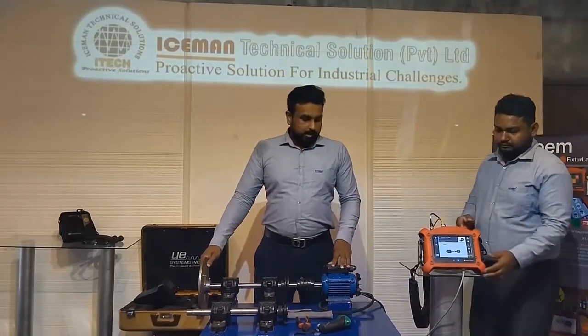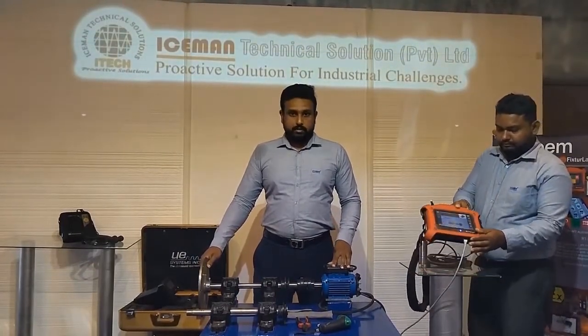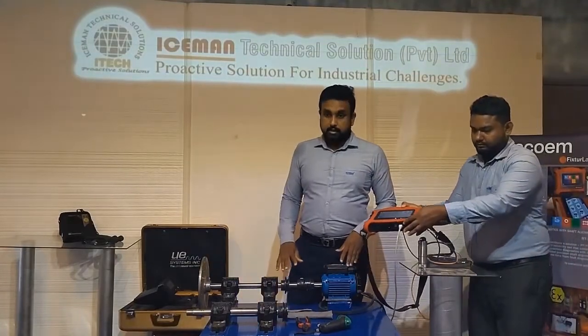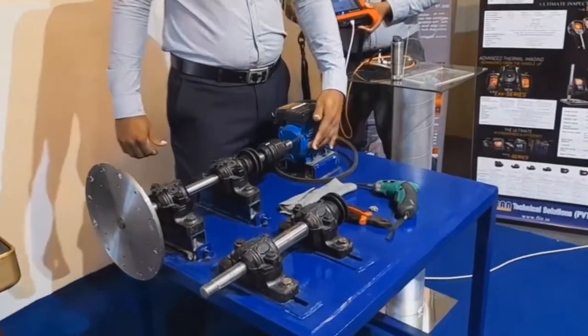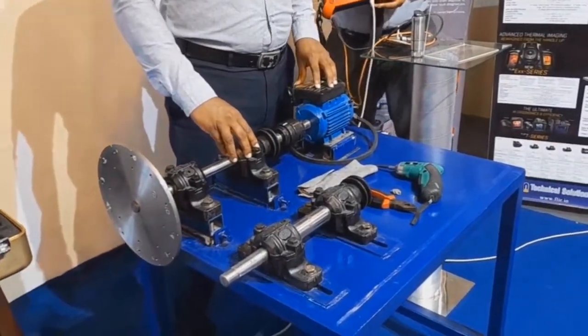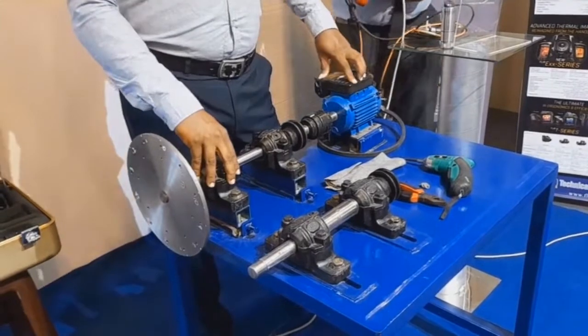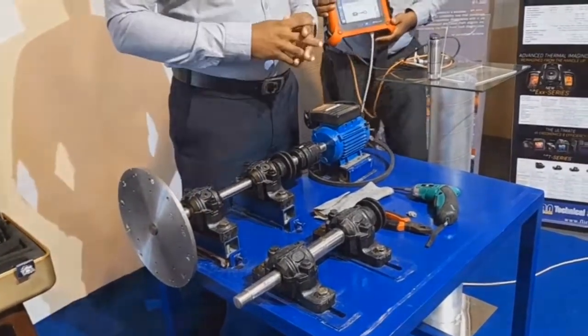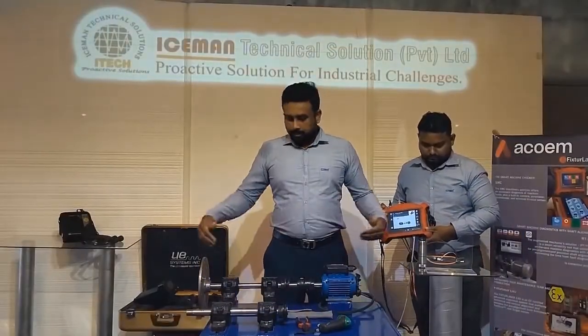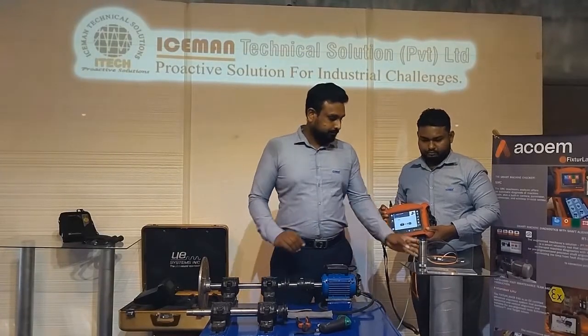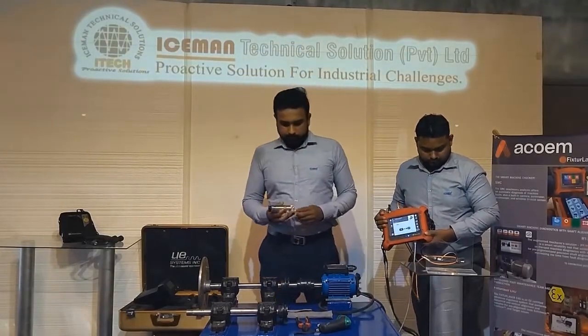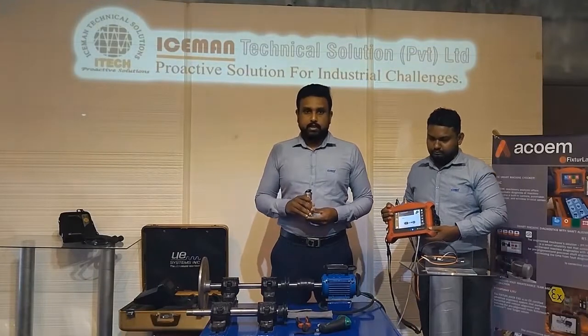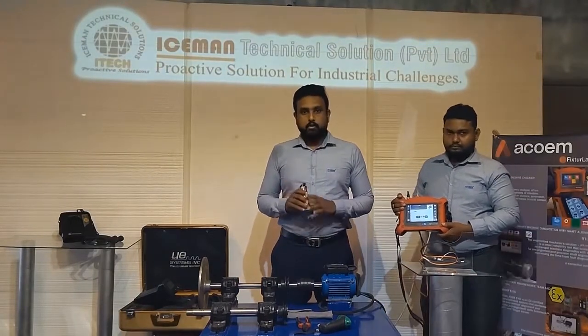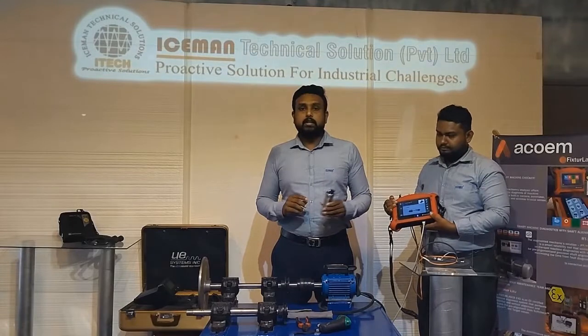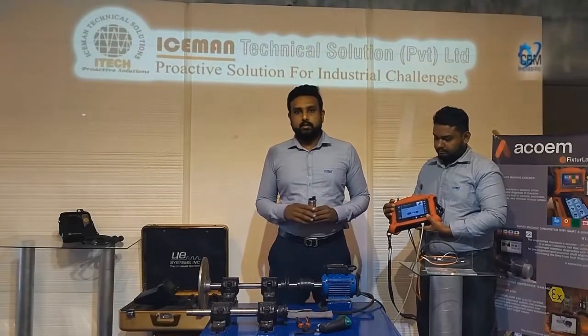Okay, now we are going to take the vibration. Before taking the vibration, I will introduce the points. First, we take the vibration at the motor non-drive end and drive end. After that, the pillow blocks, first pillow block and second pillow block. Now we are going to take the vibration in this system. Remember, when you are taking vibration, you have to take the vibration measurement at full RPM, in the running condition of the system.